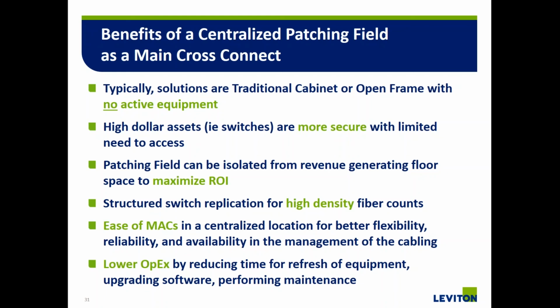The centralized patching field should replicate the switches or respective equipment device port for port, making moves, adds, and changes structured, easy to access, and scalable. The centralized patching field does not have to be centrally located, like how it was shown in the last slide. The patching field does not require power or cooling, so it can be located away from all the active equipment in its own floor space or isolated in a separate room. The premium floor space of a data center can and should be utilized for revenue-generating cabinets, housing switches and servers, to maximize your return on investment.